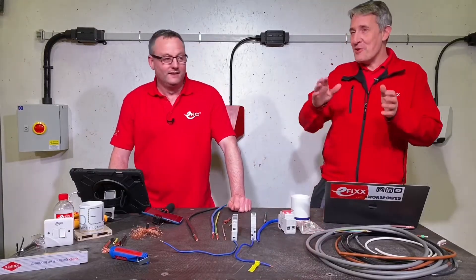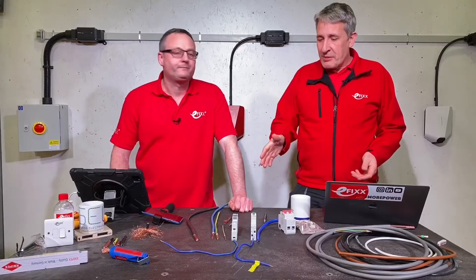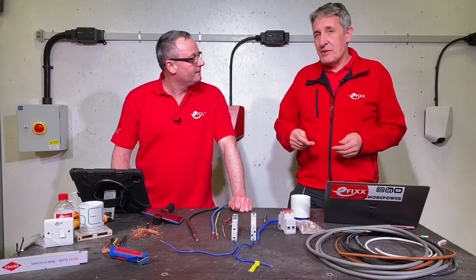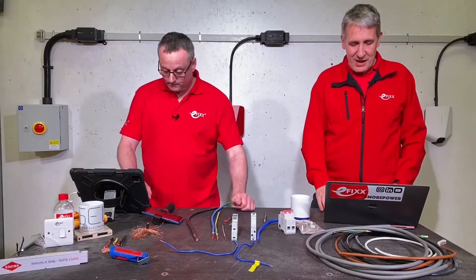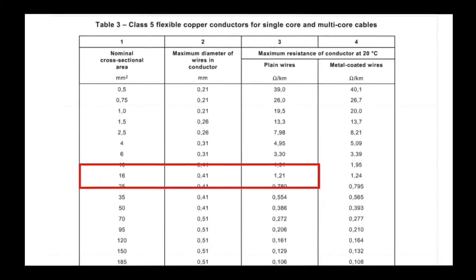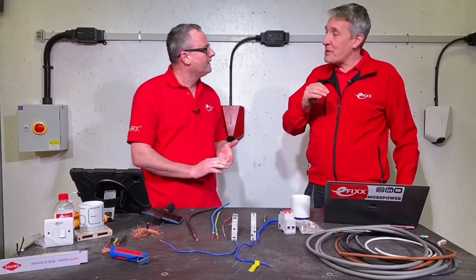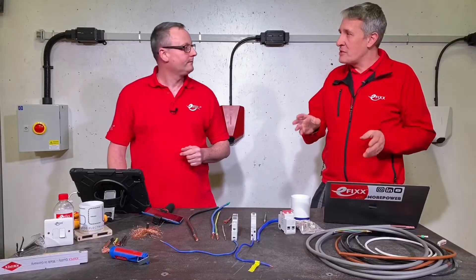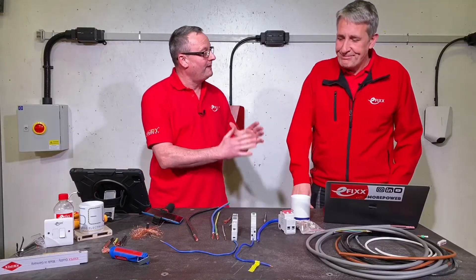That's a lot of strands — more than I thought would be in there. So that's a tri-rated cable. The same classified conductors are used in flexible cables. Obviously the bigger the cable, there tends to be more individual strands, and the maximum diameter of those strands is defined in the regulation. For a class 5, 16mm conductor, the standard doesn't tell you how many conductors have to be in there, but it does tell you the maximum diameter and it defines the resistance of the cable.